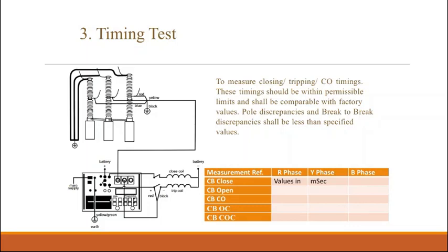Here I have taken the maximum possibilities. One is breaker close condition, how much time it will take. For open condition, how much time. In the bottom three, the close-open, open-close, close-open-close. These three are mainly required for the auto recloser function.